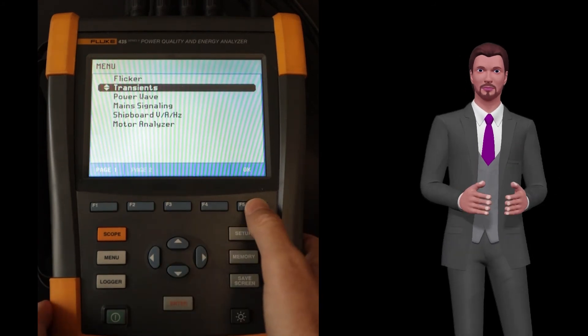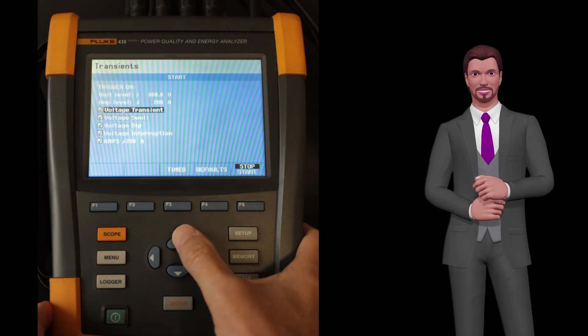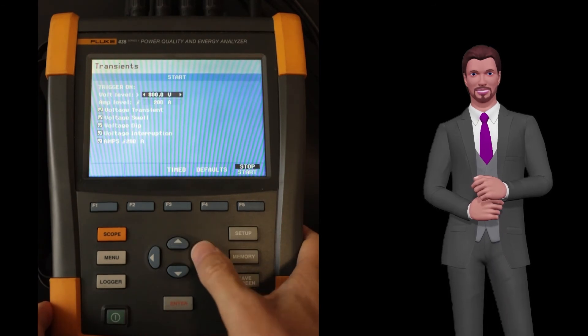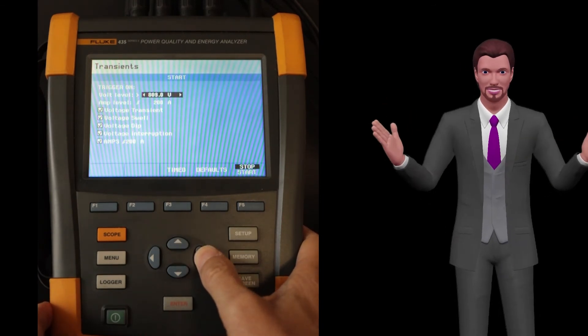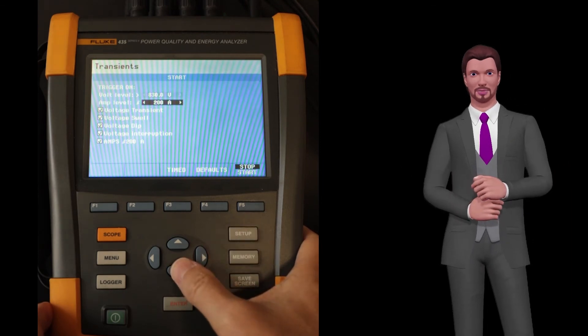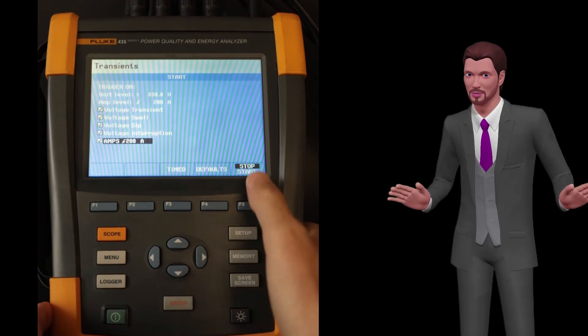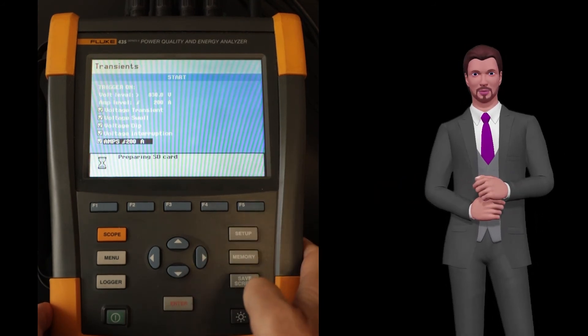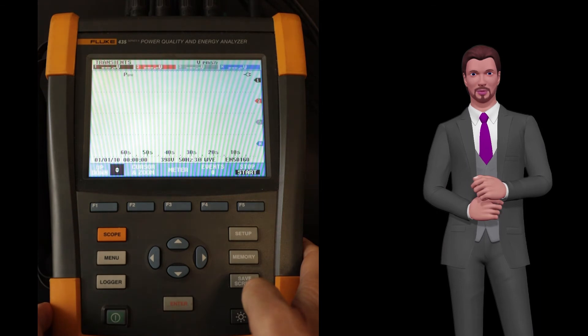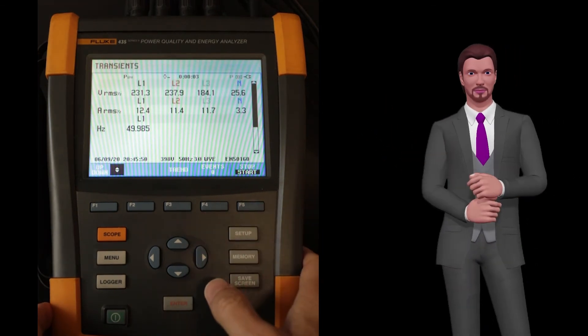The next function, transients, puts the equipment in a high-speed sampling mode that allows capturing fast voltage transients up to 6000 volts with a duration as small as 5 microseconds. In this mode the unit saves the waveforms associated with these transients, which can later be analyzed graphically with cursors to determine the duration and magnitude of the transient in order to define the appropriate protection.